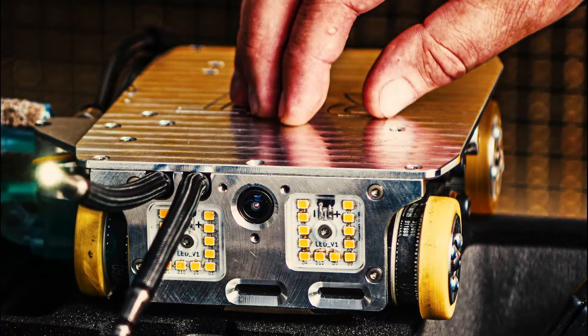The inspections at SONGS utilize three robots. The first robot enters through the inlet air vent and delivers a smaller pneumatic robot that uses suction to crawl over the canister surface. The third robot provides additional visuals of the process. The camera is used to capture 97% of the canister shell surface, as well as the interior of the storage module.